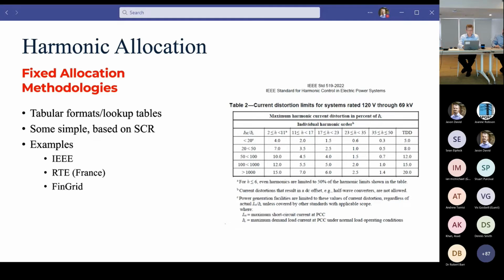So firstly, the fixed allocation methodology. Like I say, IEEE 519 is a good example of this, but there are also different methodologies in use in France by RTE, the TSO in France, and FinGrid in Finland has quite a different approach. Ultimately it all comes down to an allocation being received by a connecting customer based on the short circuit ratio of the installation, or to put it a different way, the agreed nominal power of the installation in ratio to the fault level of the network at the point of connection itself.